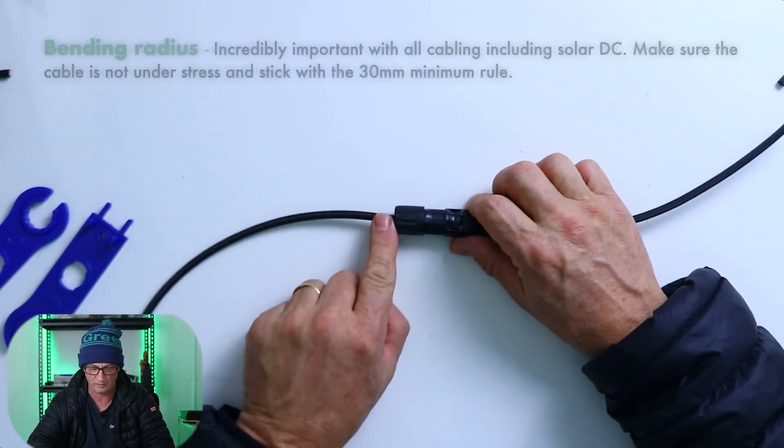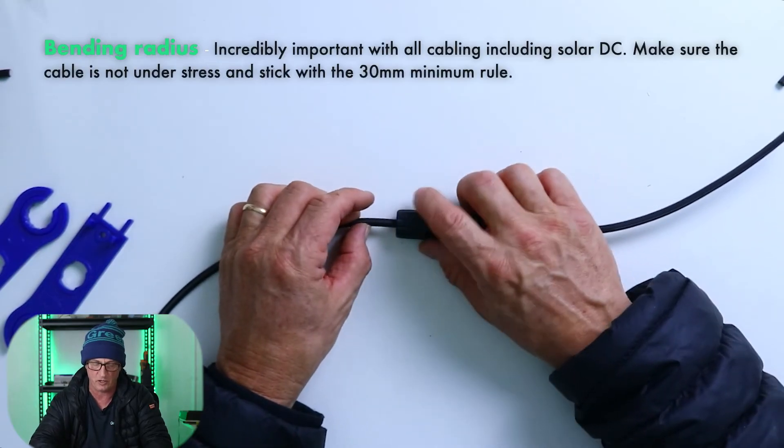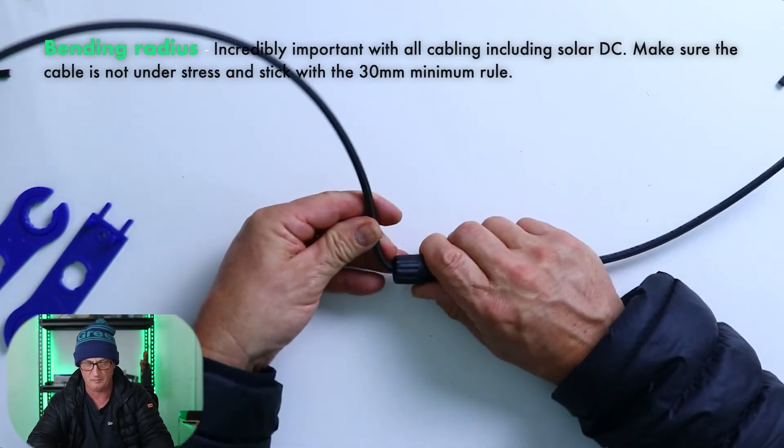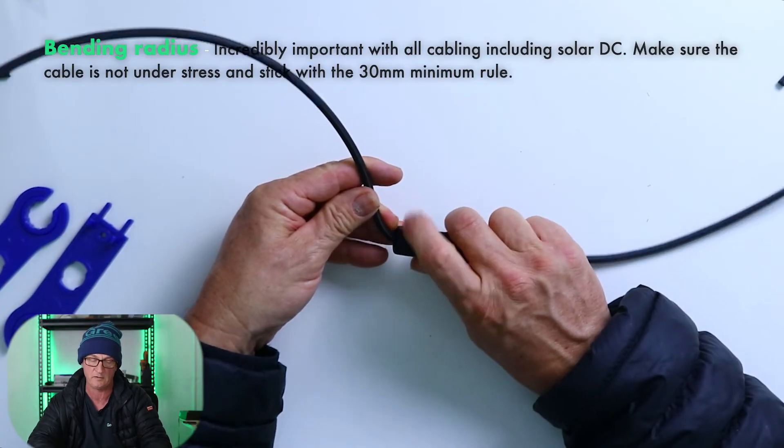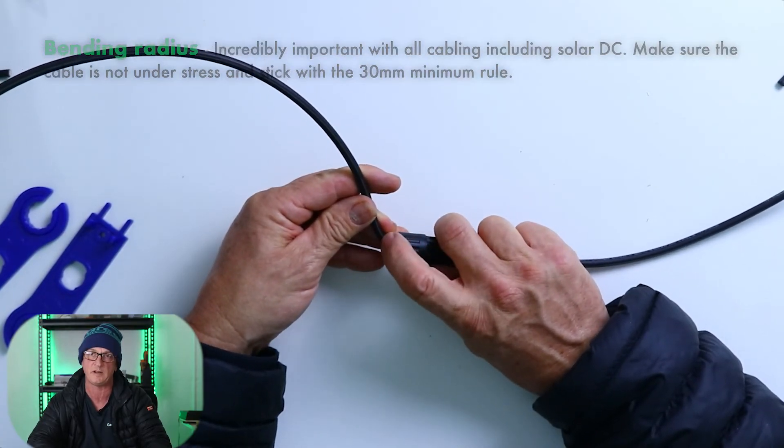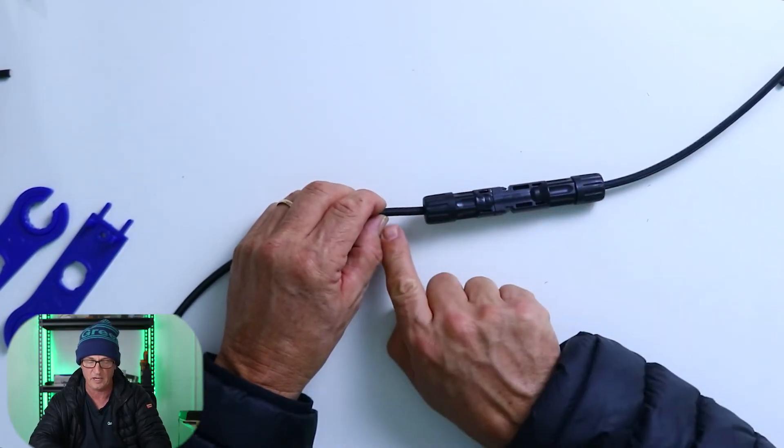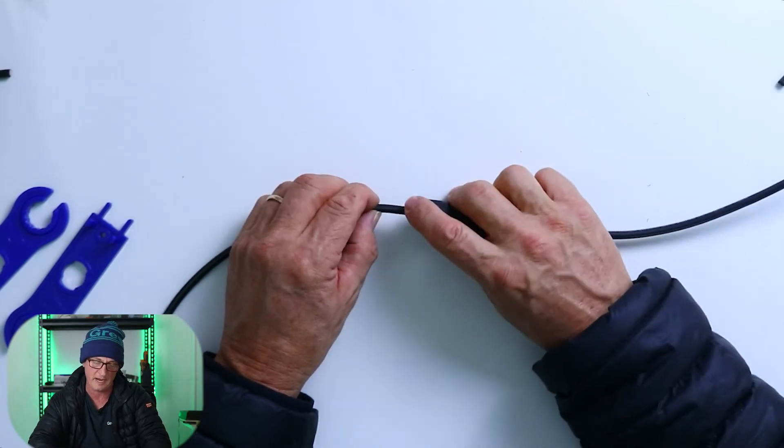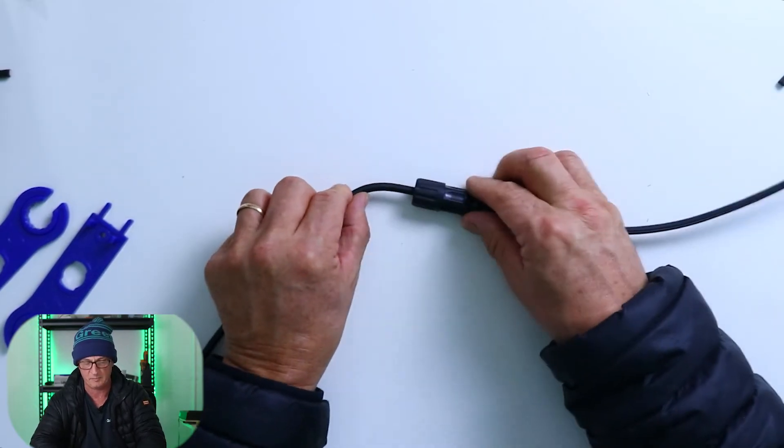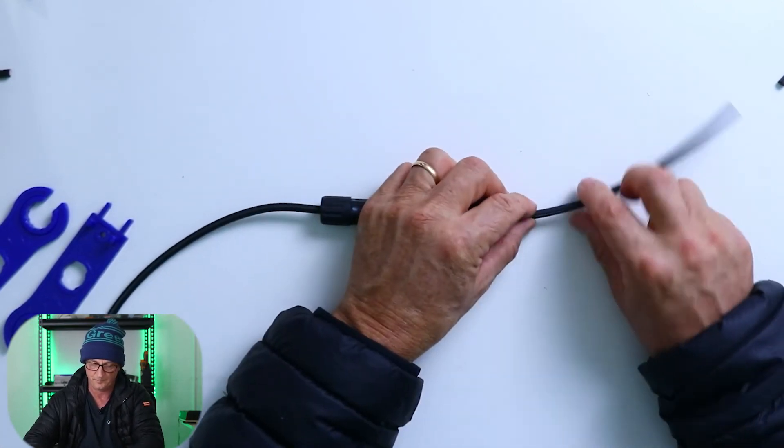A couple of really important points. Bending radiuses of cable. You see this in a lot of jobs where people have bent them like this. Don't do that. You'll start breaking strands and you've gone past the bending radius of this 6mm cable. Rule of thumb is allow at least 30mm outside the actual end of the MC4 before you start bending. That's acceptable.